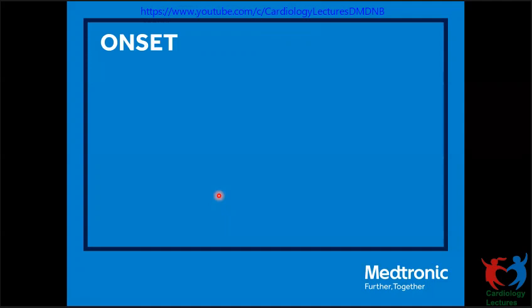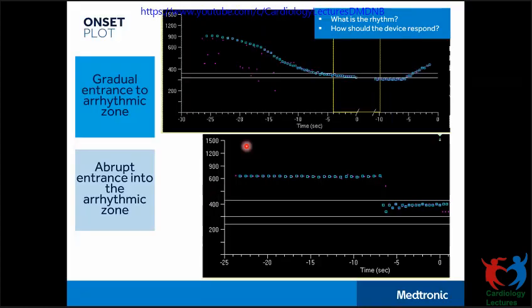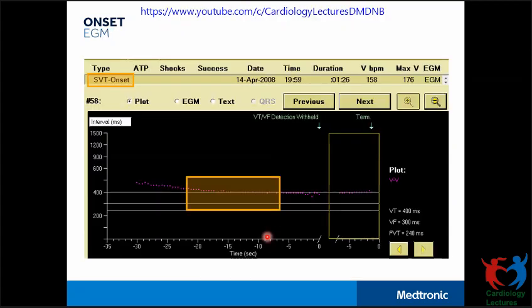Moving on to the Onset discriminator. Looking at the plot diagram, one rhythm begins gradually whereas a second rhythm begins abruptly. The onset feature prevents detection of sinus tachycardia as VT by evaluating the acceleration of the ventricular rate. If the ventricular rate increases gradually, as seen during sinus tachycardia, the device classifies the rhythm as SVT due to onset.